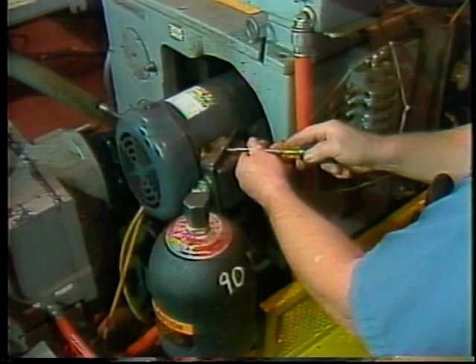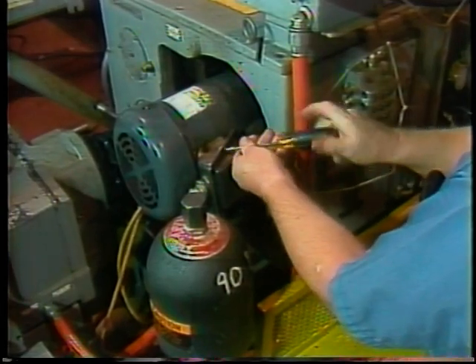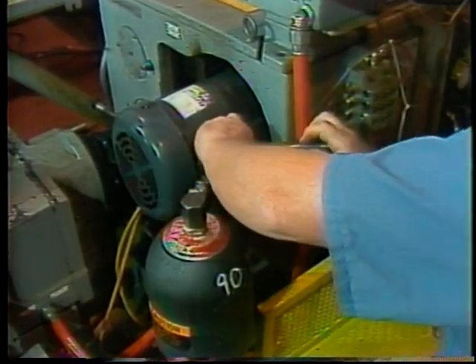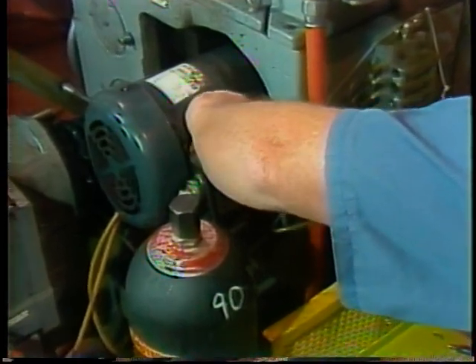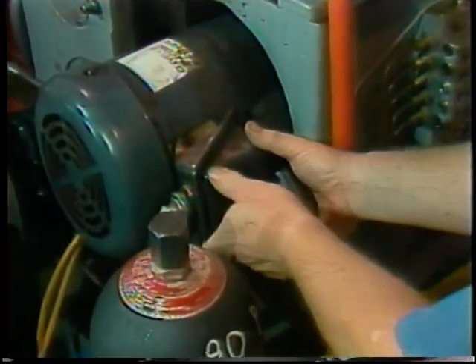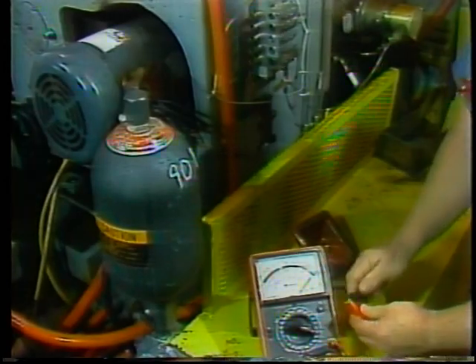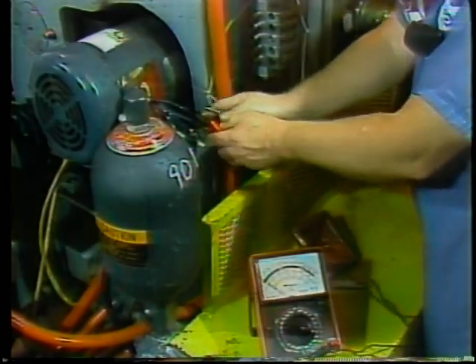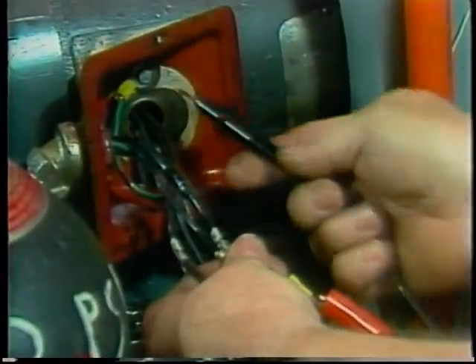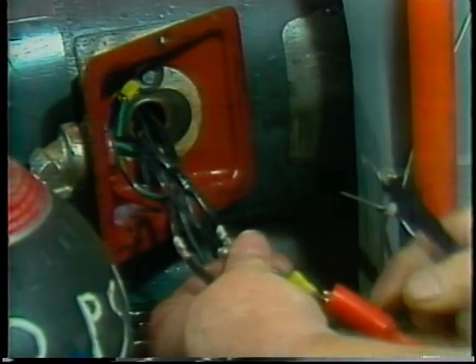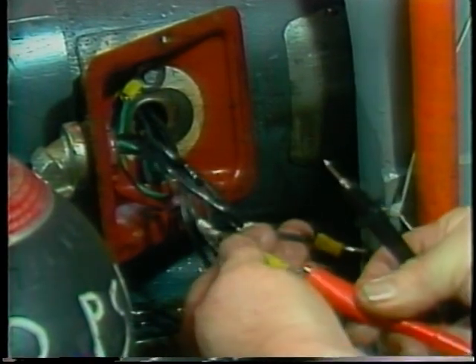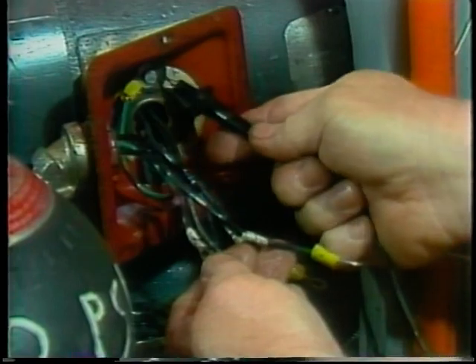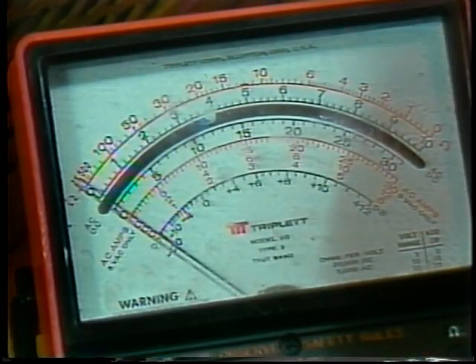Resistance readings will sometimes pinpoint electrical problems in the motor. Lock the motor out first. Disconnect the power lines. Occasionally, a 3-phase motor will also have a neutral as well as power line connections. Disconnect it too. Then check resistance between the motor frame and the motor leads. Use the highest ohm scale. On most simple ohmmeters, anything but an infinite reading is a sign of some kind of short to ground.